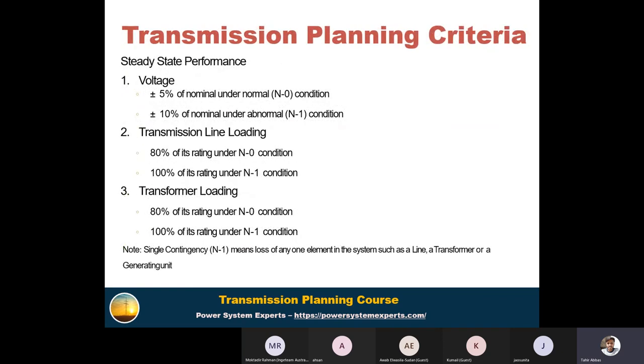Okay. So the first input in transmission planning is the transmission planning criteria. We are clear that the policymaker is developing a transmission plan for the next 5 years, or the next 10 to 20 years. So what are the criteria? Basically, technical criteria. The first criterion under steady state performance is voltage. Voltage of each grid and substation under normal condition, like N minus zero, meaning all components are in connection, has a threshold of 5% of the nominal voltage, meaning from 0.95 to 1.05. This is the range where voltage is in the acceptable range.